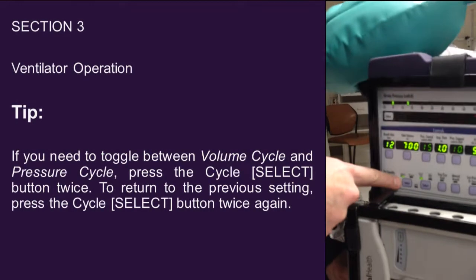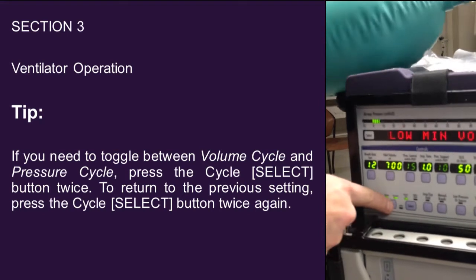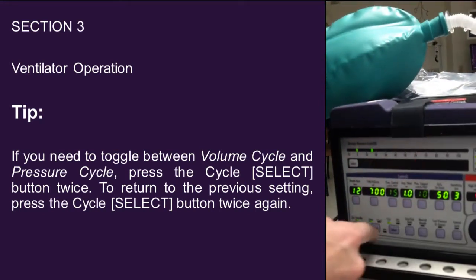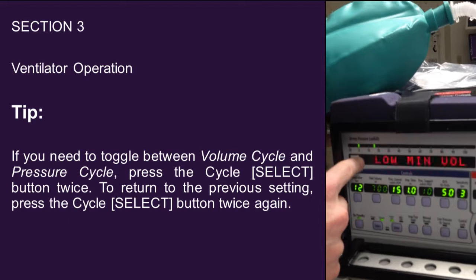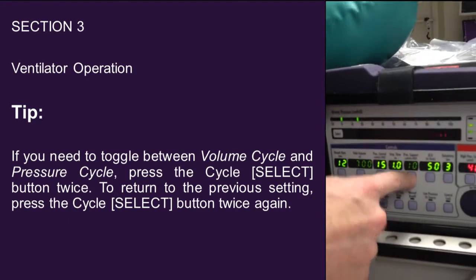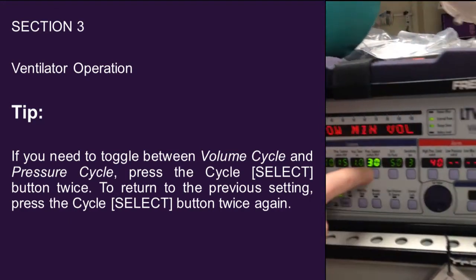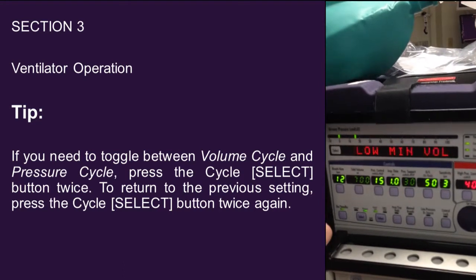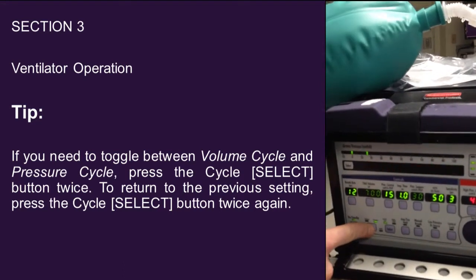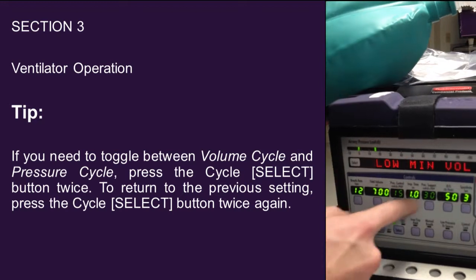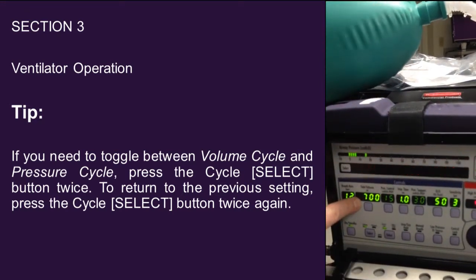Sensitivity, don't worry about that. And here's your high pressure limit. Low pressure limit. Again, you can set that. I'm going to turn that down for right now. Low minute volume. Again, I'm going to turn that down for right now. This is volume cycled. If you want to switch to pressure cycled, this is now switched to pressure cycled, and now you can decide how much pressure you actually want in. So now this will just go to a pressure of 30. Want to select back to volume. Now this is back to volume as we had it set with a tidal volume of 700.